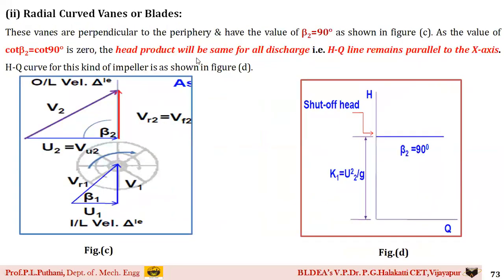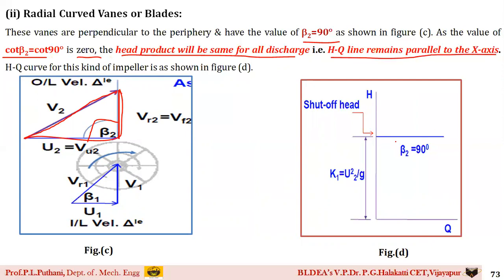The second case is radial curved vanes or blades, where β₂ = 90°. When β₂ = 90°, the outer velocity triangle becomes a right-angle triangle, and cot 90° = 0. Therefore, whatever the discharge, the head remains constant — the H-Q curve is a horizontal line parallel to the x-axis. In graph D, as Q increases from the origin, the head value remains constant. So for radial curved blades, increasing discharge produces no change in head.